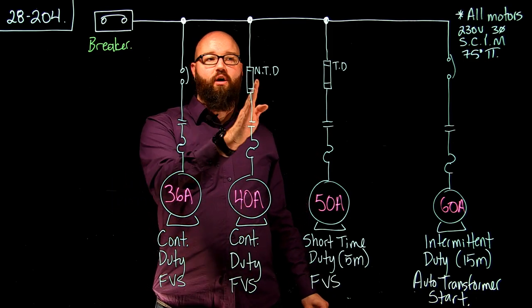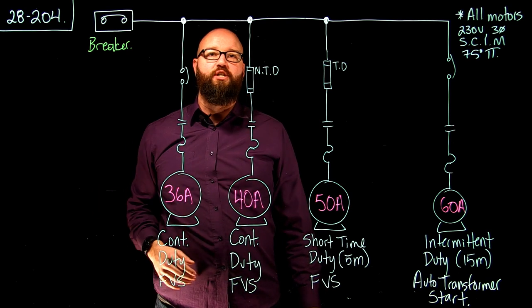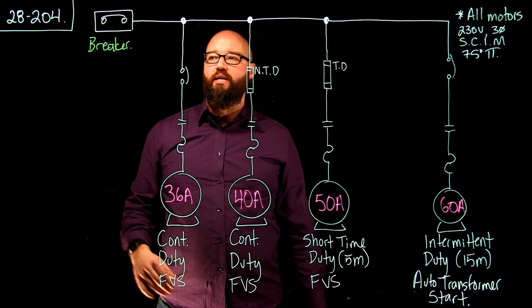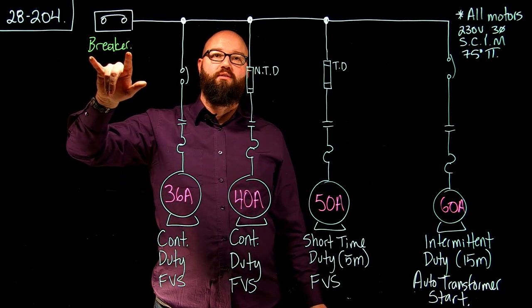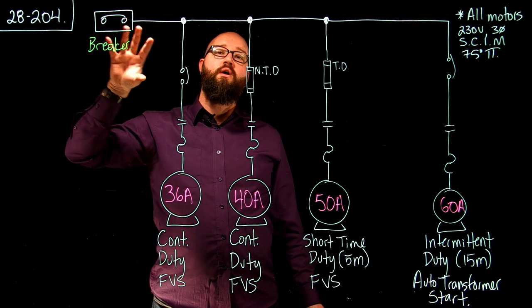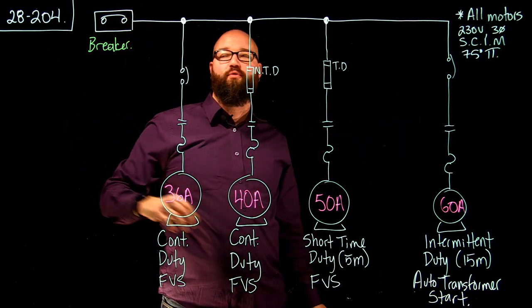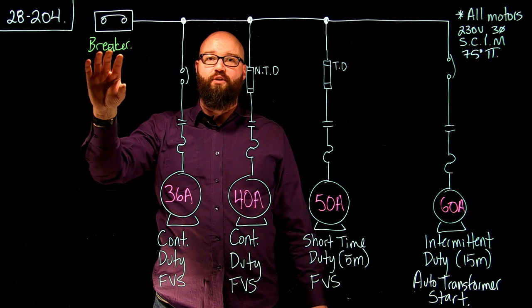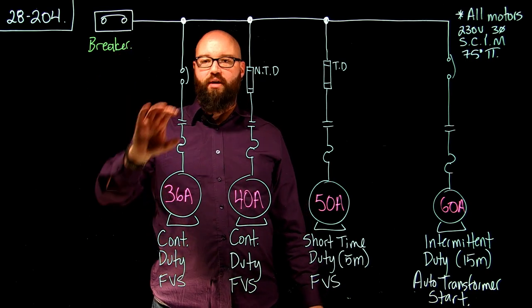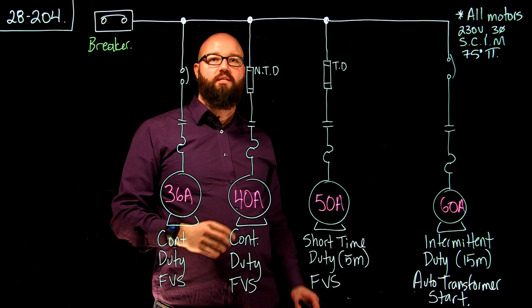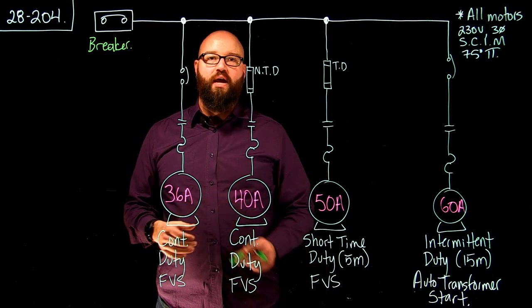We are going to disregard what the overcurrent device is on each one of these branches and only focus on breakers. If I had a non-time delay fuse, I would apply the multiplier for a non-time delay fuse to each one of these branches. And if I had a time delay fuse, I would take the FLA times the multiplier for a time delay fuse.